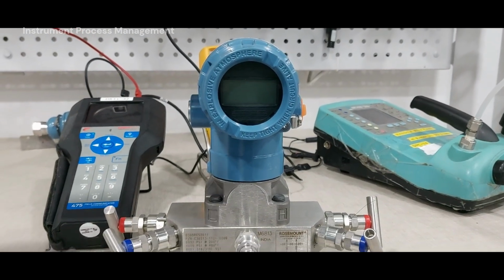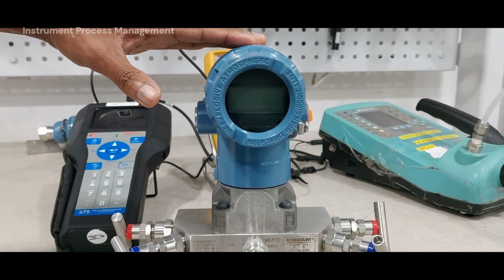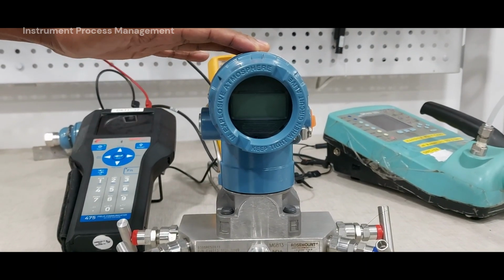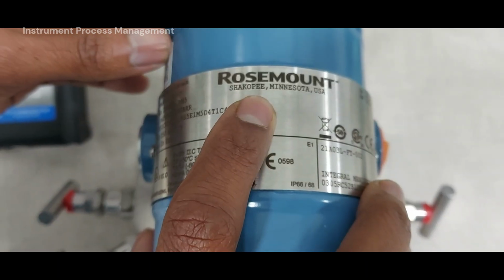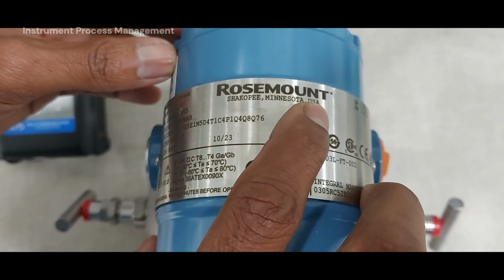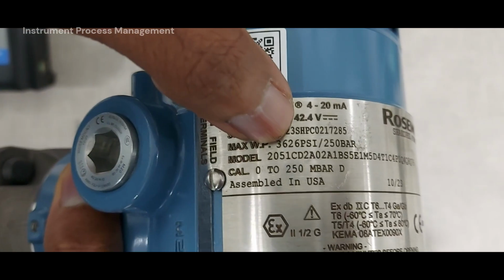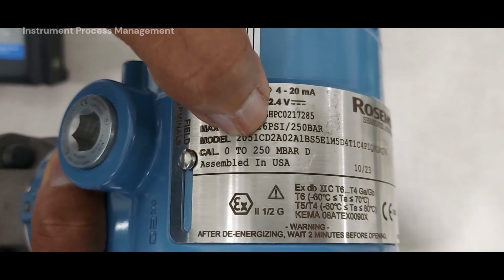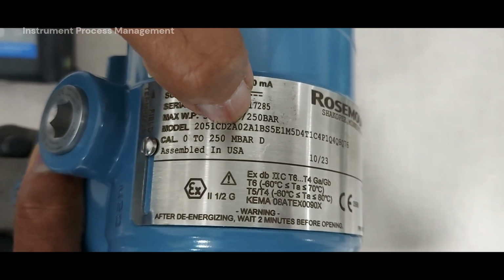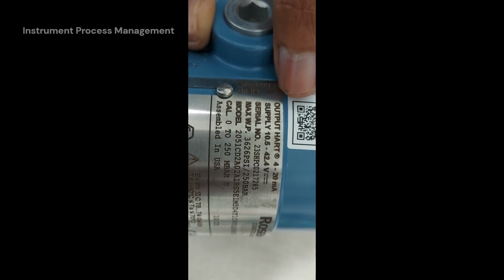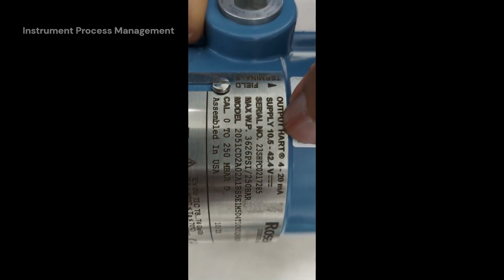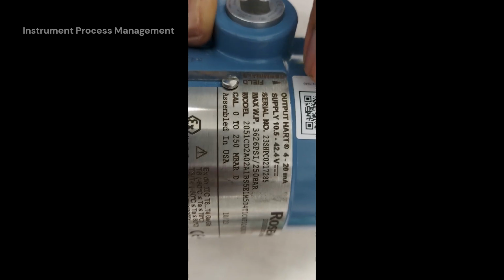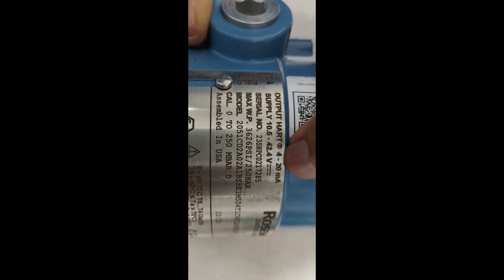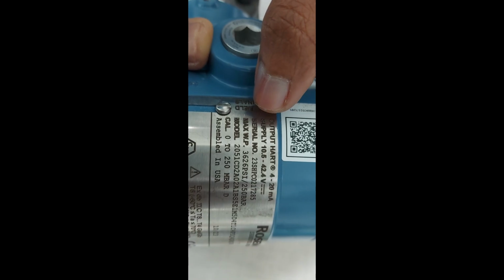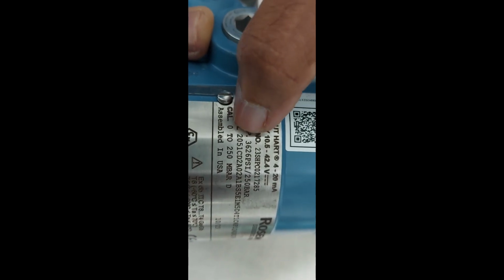Today we are introducing the DP type flow transmitter calibration and configuration procedure. Manufacturer: Rosemount. Instrument model number 2051 CD2A. Transmitter communication protocol HART. Transmitter output range 4 to 20 milliamps. Instrument calibration range 0 to 250 millibar differential.